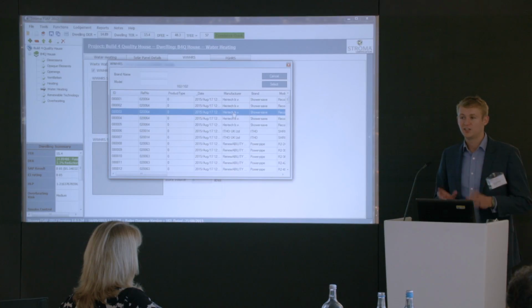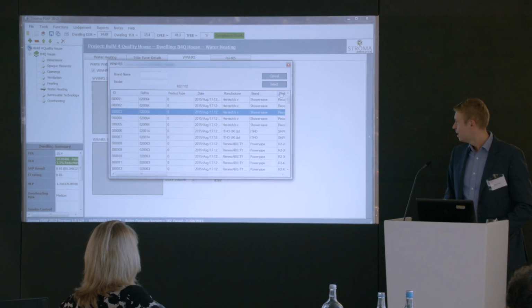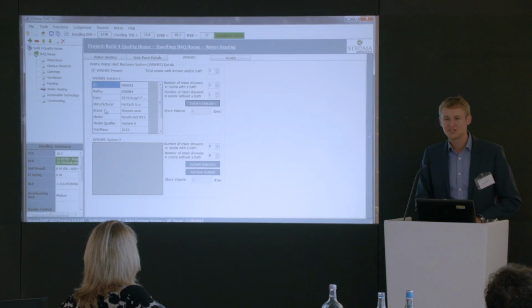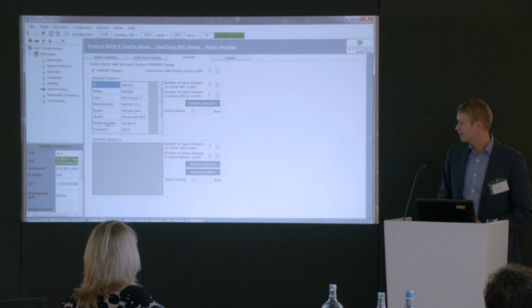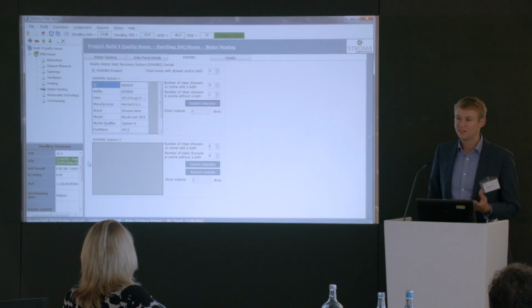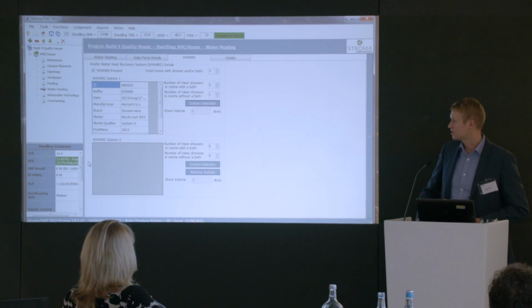It doesn't recirculate your shower water. I have heard a few people express concerns on that. It's just the heat. But in this property, we have a reasonable water demand here, so it's actually made quite a big improvement. It's been about 7% in this case. Now, cost-wise, I think they're about £500 to £700, something like that. It can add up, and it can be a way to start chipping away at the regulations.